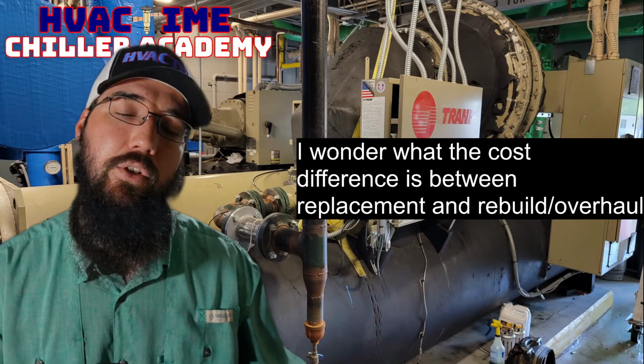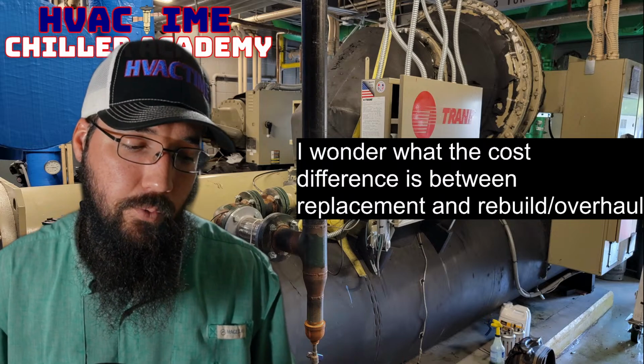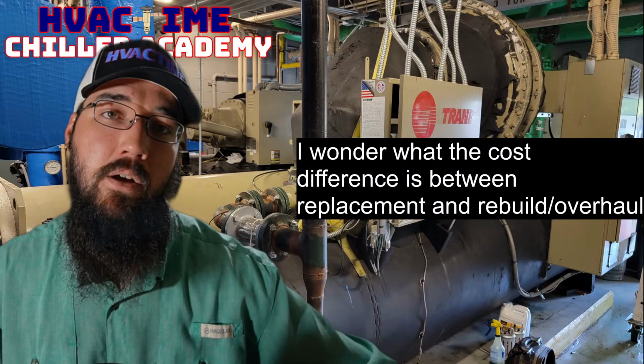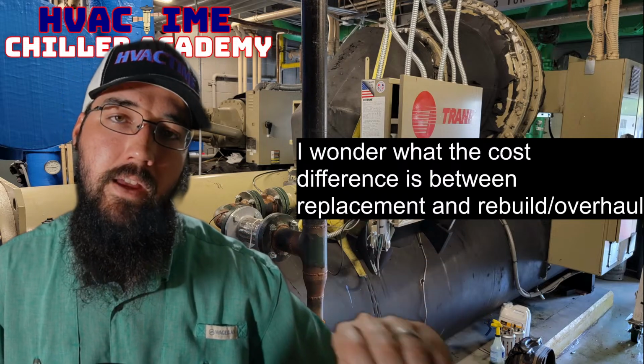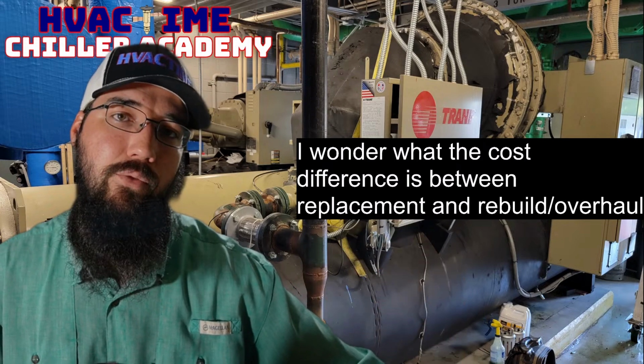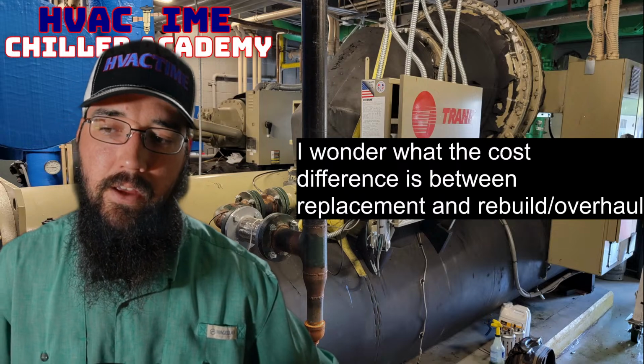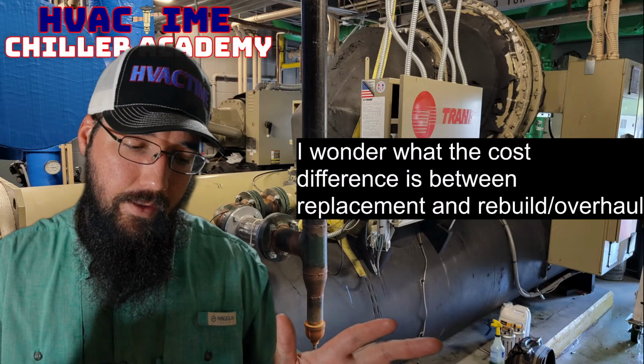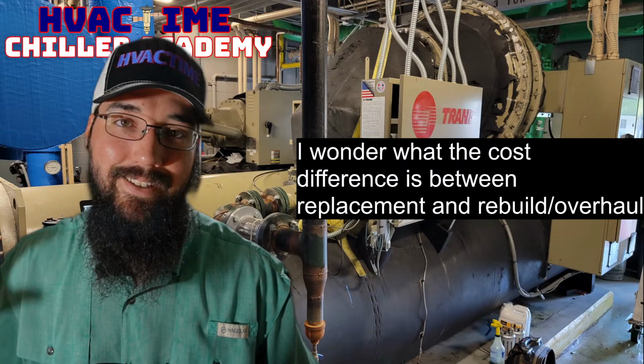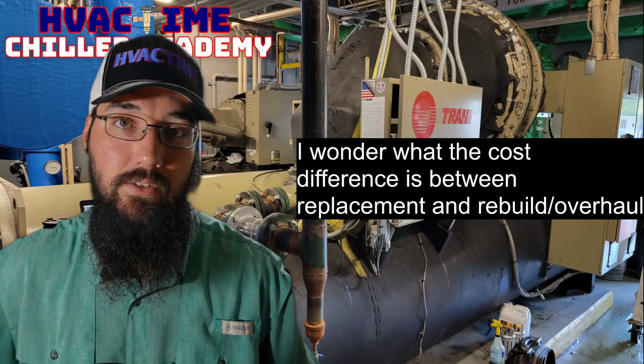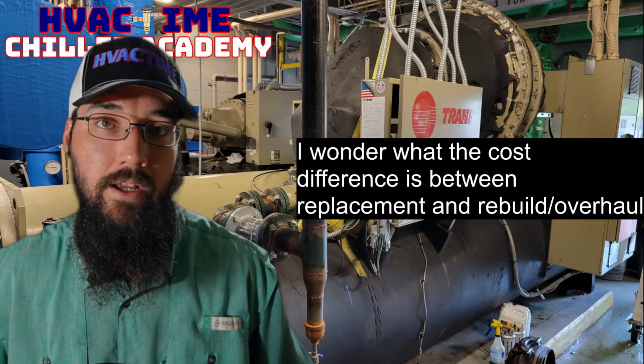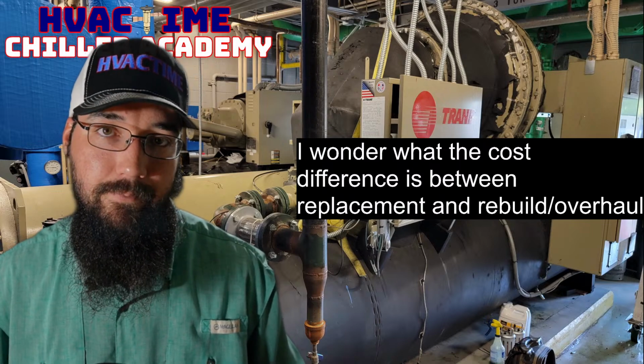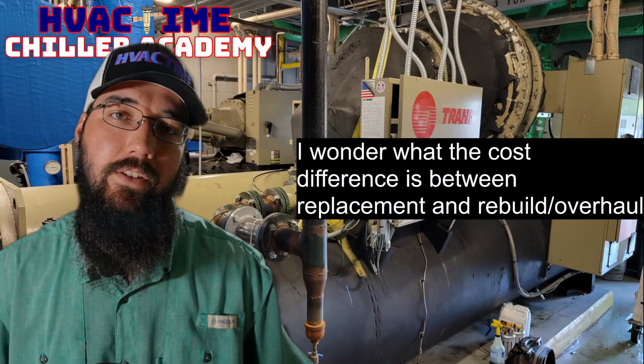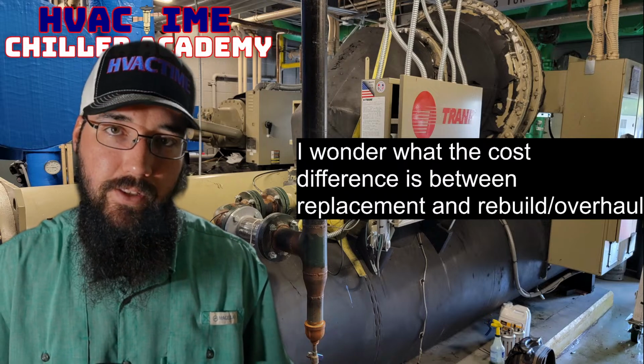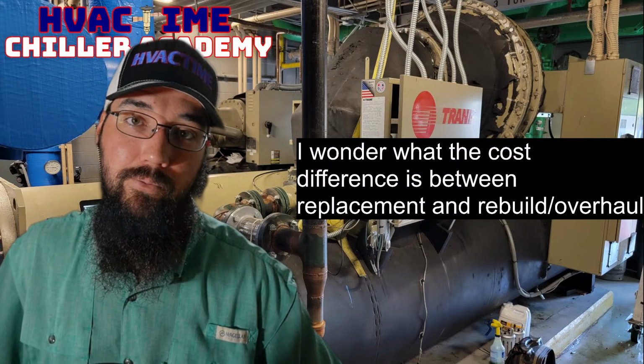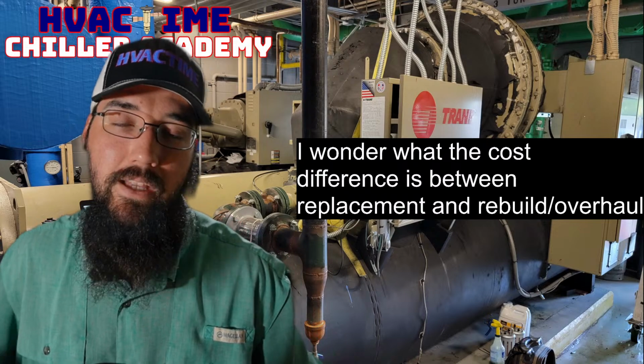But the faster option, in a lot of circumstances, ends up being the big thing. When you have a conversation like, it's going to take a month to do this overhaul, and within a month and a half you could be back online in an extreme case, versus it being 6 to 8 months, if not a year plus, before the machine's even built at the factory, much less shipped and installed, that timeline alone is enough to make most critical facilities say buying new just isn't going to work.